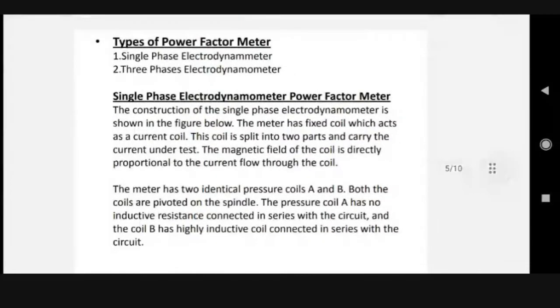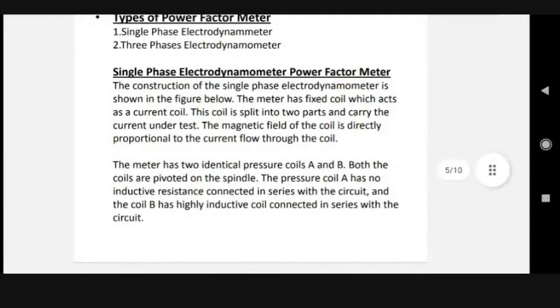The construction of a single phase electrodynamometer is shown in the figure below. The meter has a fixed coil which acts as a current coil. The coil is split into two parts and carries the current under test. The magnetic field of the coil is directly proportional to the current flowing through the coil.